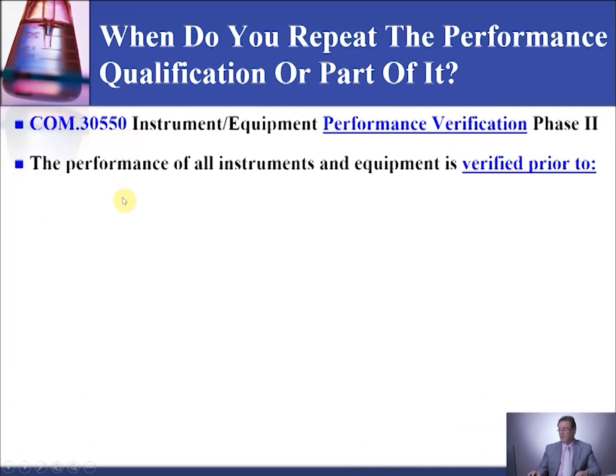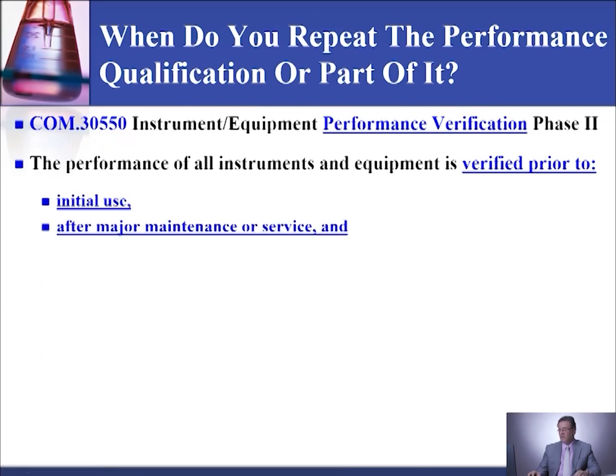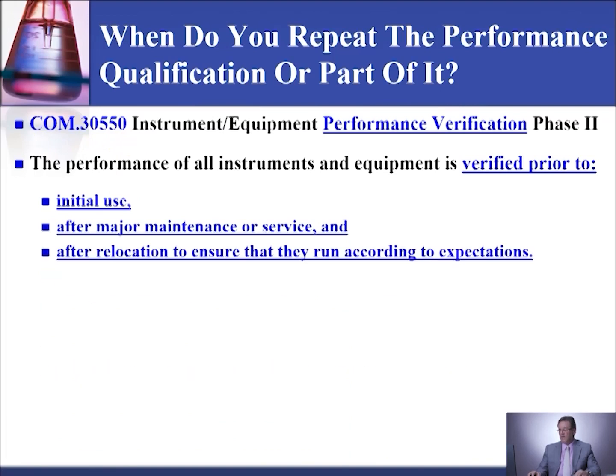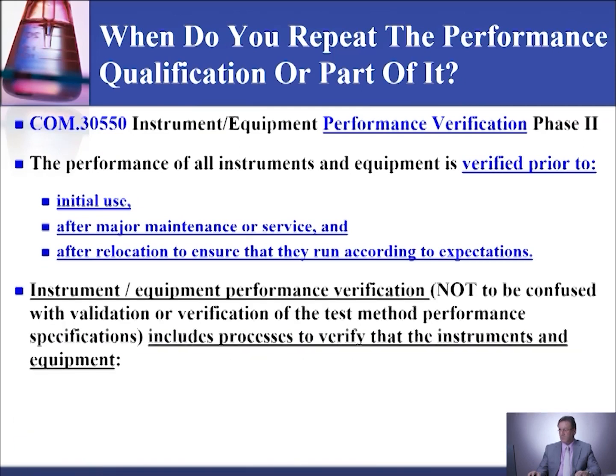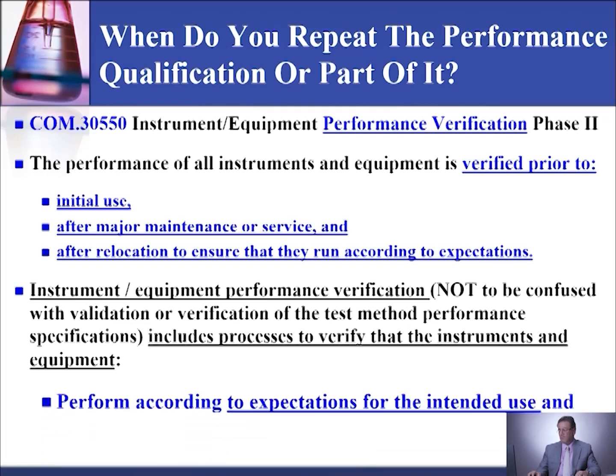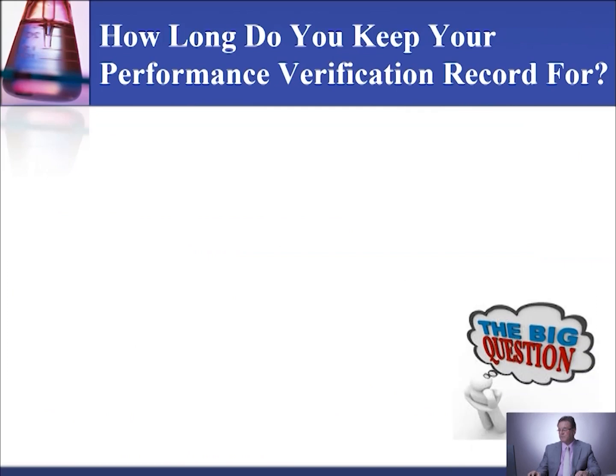COM.30550 from CAP: the performance of all instruments and equipment is verified prior to initial use, after major component replacement or service, and after relocation to ensure that they run according to expectation. Instrument and equipment performance verification includes a process to verify that the instrument and the equipment perform according to expectation for the intended use and within defined tolerance limits.